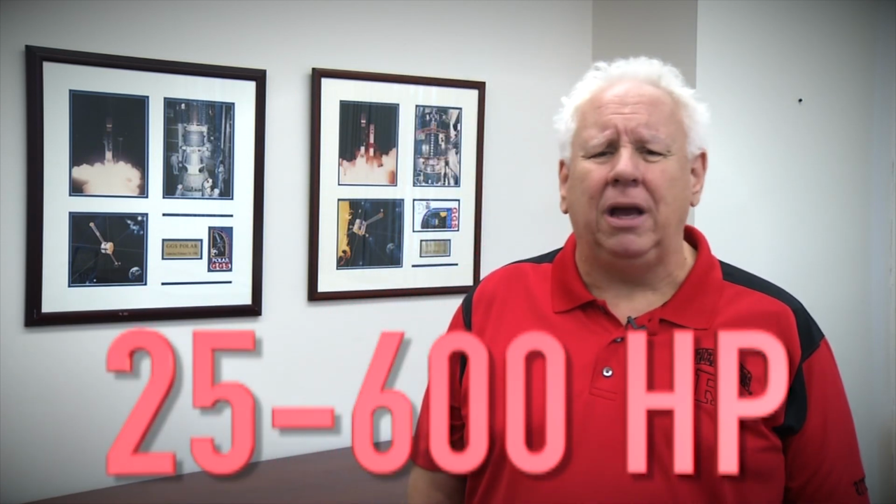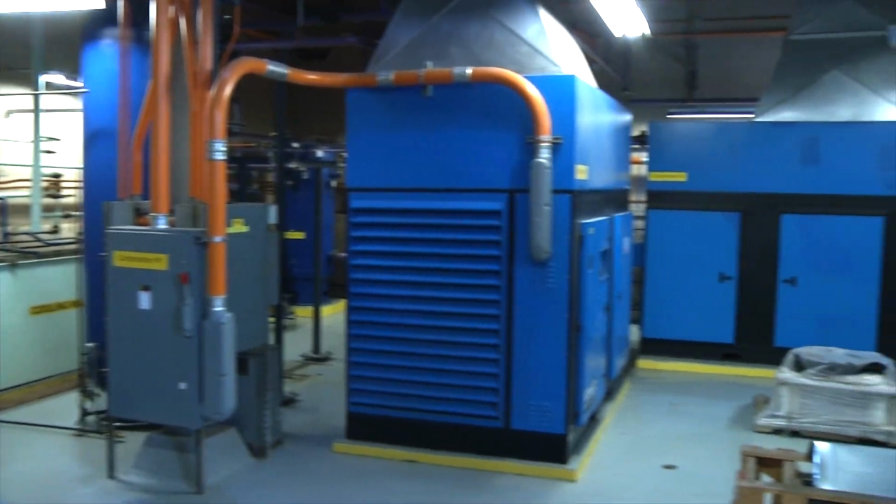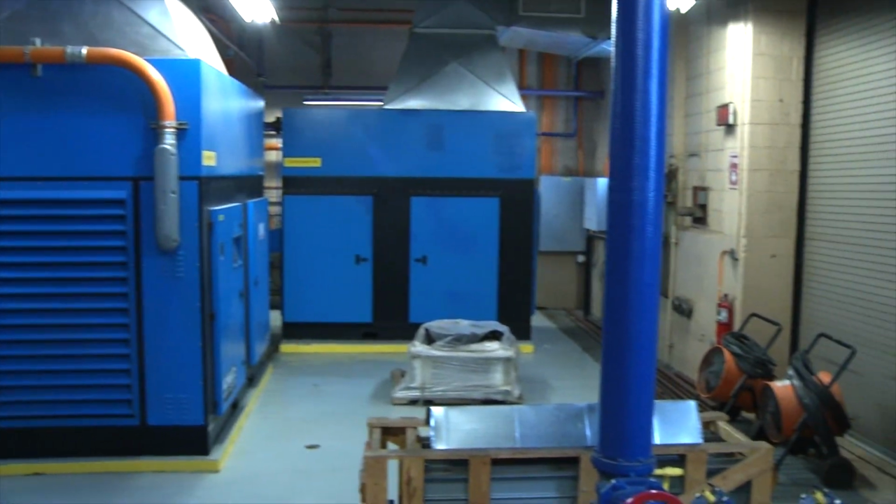Often you can improve the performance of a compressed air system by 20 to 50% with some simple and relatively minor fixes. The IAC program deals mostly with factories that are already operating, so they already have compressed air systems in place. For small and medium-sized factories we serve, these compressors can range anywhere from 25 to 600 horsepower, with the average being about 100 horsepower. So let's visit the compressor room and identify the what and why of what is there. And we begin with the compressor itself.